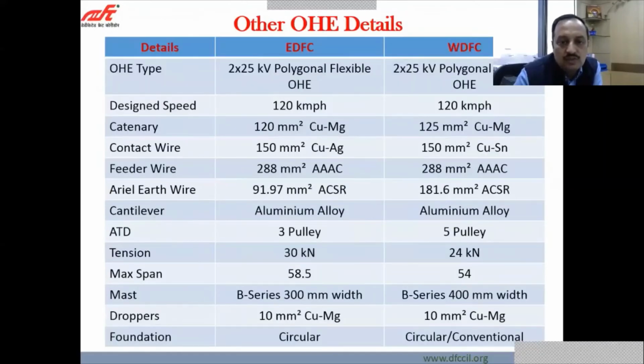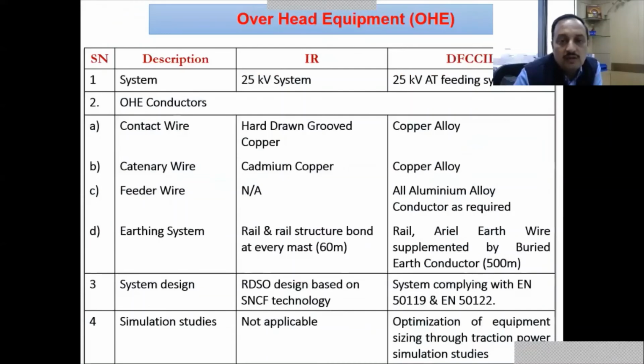These are the other OHE parameters given here. If we compare with Indian Railways, our system is entirely different, because in Indian Railways it is 25 kV and here it is 2 into 25 kV. Contact wire is different, catenary wire is different, feeder is different, earthing system is also different from IR, and our system is mainly complying with EN 50119 and 50122.